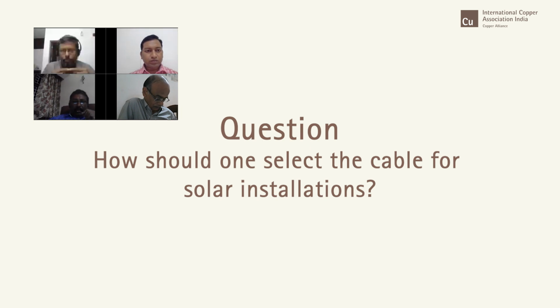But this is applicable for the connection to the DC side of the installation. So there are UV resistant cables, and they are also the FRLSH type. All these grades are FRLSH types. Even for the AC side, wherever cables are being used, FRLSH type cables are recommended, because IS 694, IS 1554, IS 7098 are all power cables for AC side applications. There are grades for fire resistance and low halogen cables available. These are the things that should be used, because during the presentations of Mr. Sivaram Krishnan and Mr. Gurumurthy, the issue of fire hazard has come up a number of times, and all these cables are also recommended by MNRE in their guidelines.